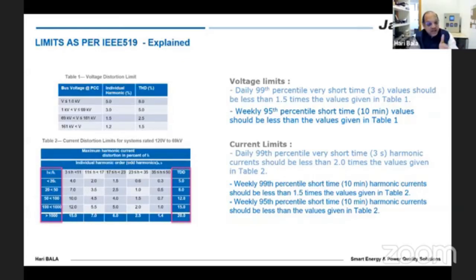And then you have the individual harmonics: 3 to 11, 11 to 17, 17 to 23, 23 to 35, and 35 to 50. So according to the ISC by IL ratio, your limits are defined. So it is very clear. For example, if a customer has an ISC by IL value between 20 to 50, then his third harmonic can be up to 7%.